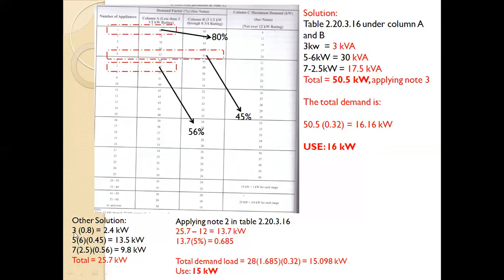Since you have three, or 3 kilowatt, times 0.8, this is the less than 3 case, so 80%, giving 2.4 kilowatt. Then five 6 kilowatt appliances times 0.45. Since you have five appliances, it falls under column B, so your multiplying factor is 0.45. Then the other one, 7, in column A, has a multiplying factor of 0.56 or 56%. So your total demand is 25.7 kilowatt.